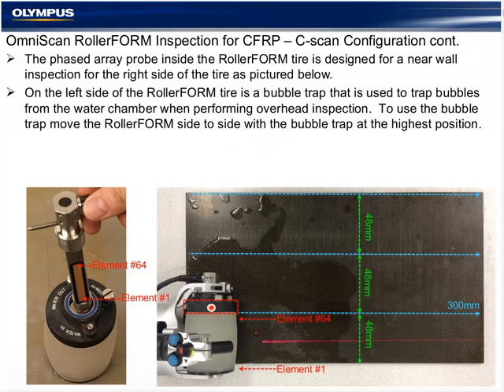Even when there are bubbles present, they only degrade the inspection on an overhead inspection where the bubbles are in between the probe and the component surface. In normal flat or even angled inspection, it's not normally a concern, but it's very easy to get rid of them using the bubble trap and the out valve as well.